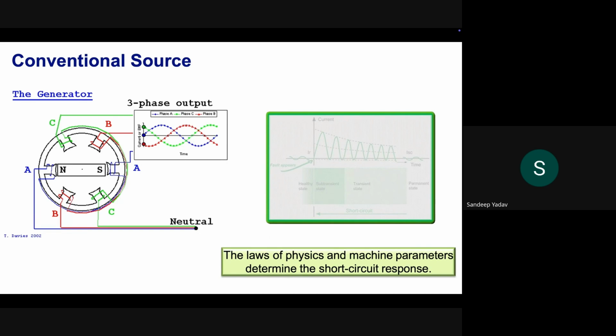This is how a conventional source reacts to a change, a perturbation, or a contingency. For example, there is a rotor rotating at synchronous speed. It has its poles, coupled with the electrical poles of the stator, from where we get three-phase alternating waves displaced by 120 degrees. A balanced three-phase wave is generated through this mechanism, and conventional sources act like a strong voltage source. When we say voltage source, it means that if you try to change the voltage, the machine resists the change in voltage.